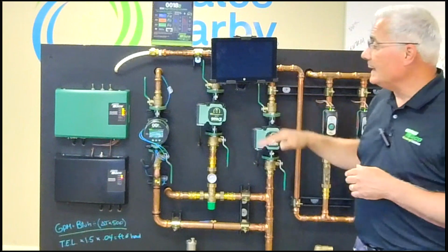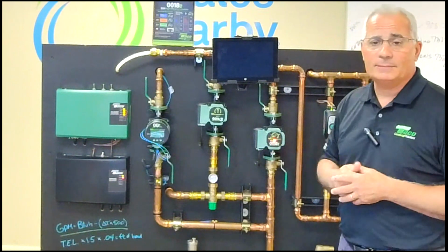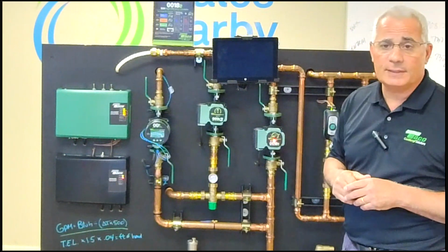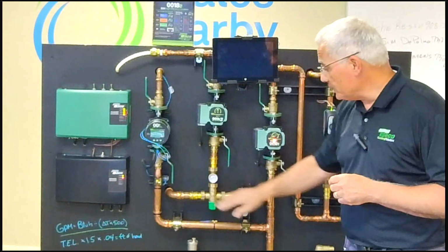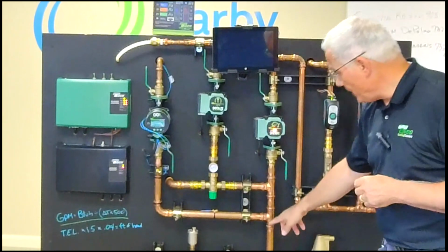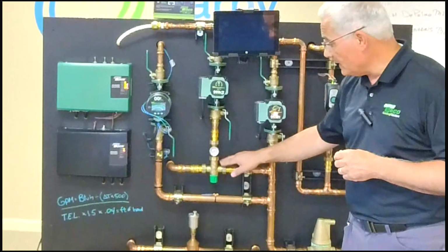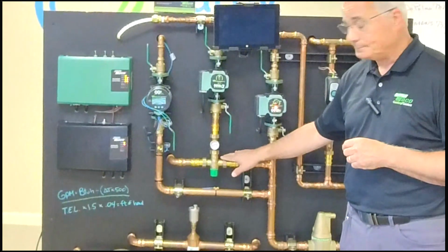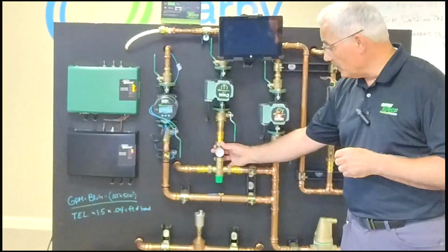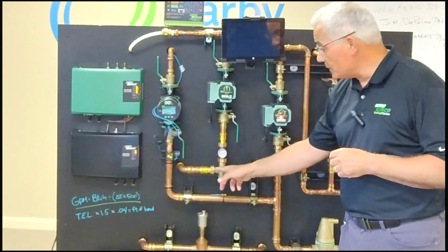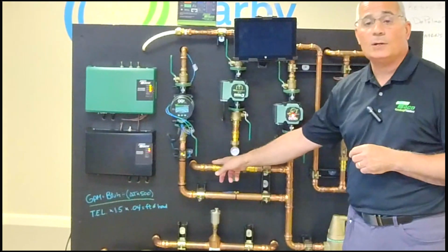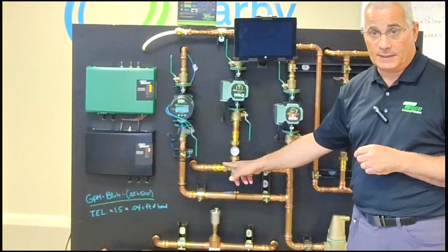I need to drop down that temperature. I need to drop it down, probably to 100 degrees. So I have my mix valve here. So you see the piping, we hit a T, we are sending our hot side to the H port. This is the mix port. And this port here is the cold port, which would be the return from that radiant side.